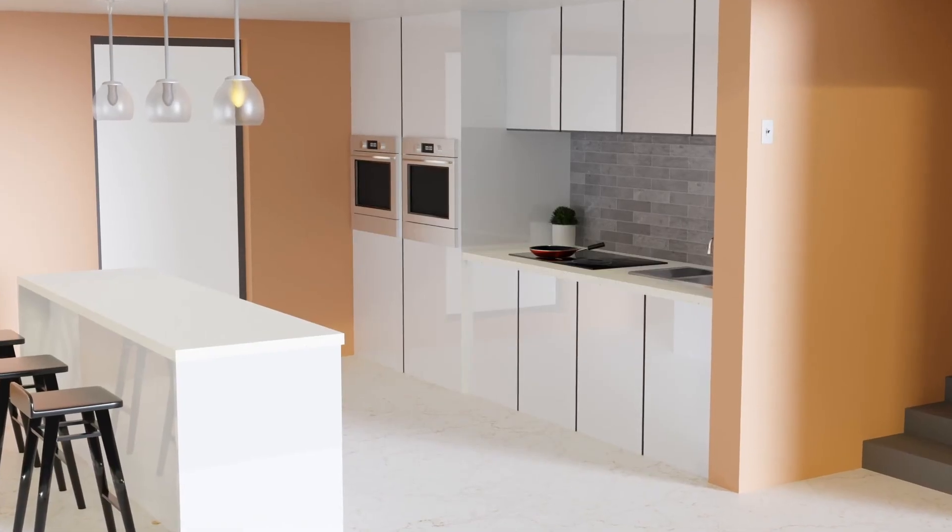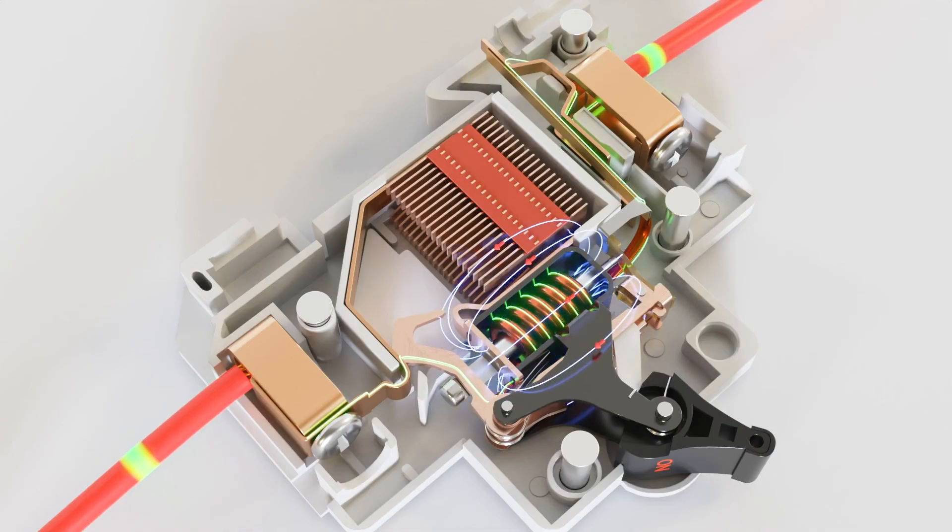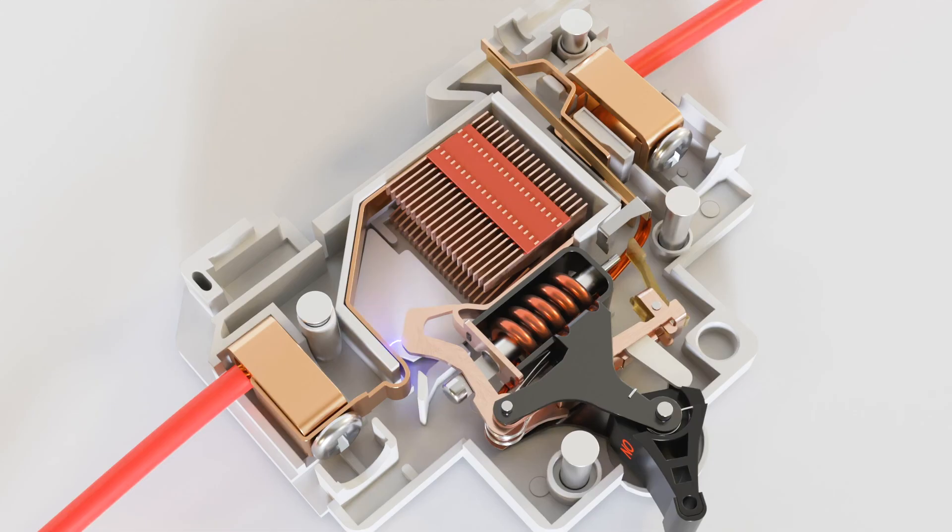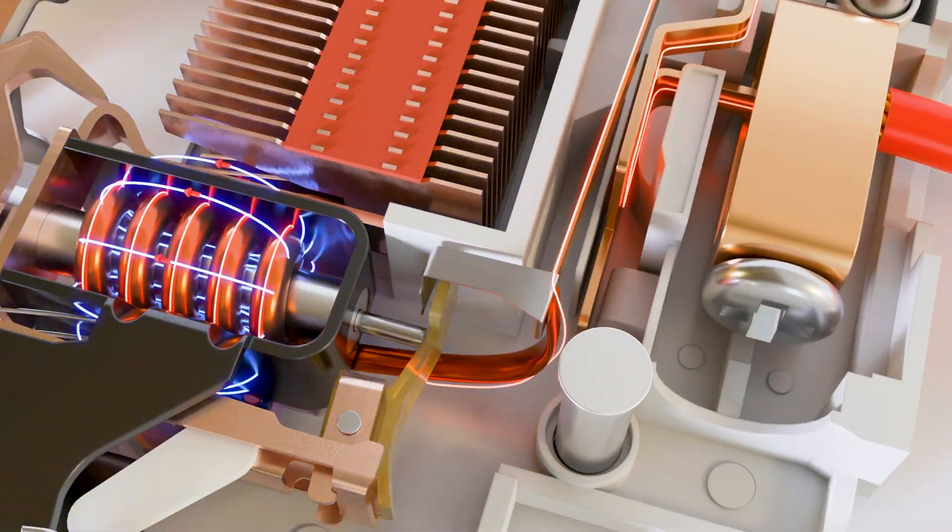Please note that a short circuit is much more dangerous than overloading. That's the reason a circuit breaker quickly trips within two to five milliseconds during a short circuit. But in case of overloading, it takes few seconds to trip.